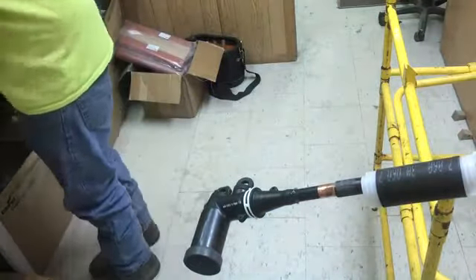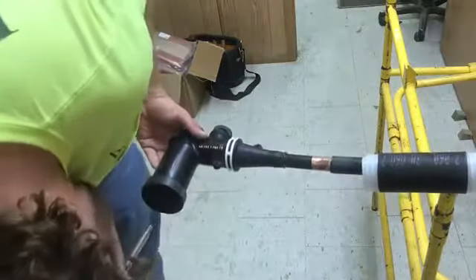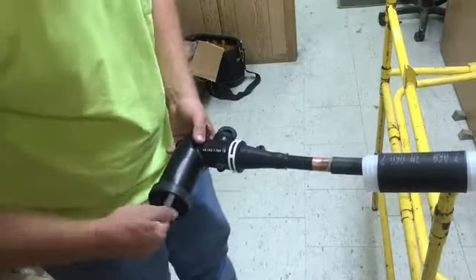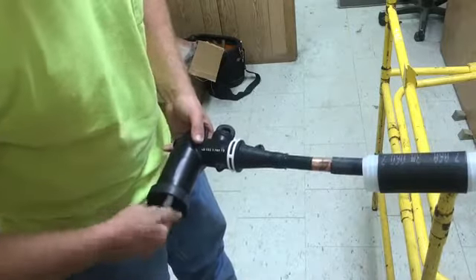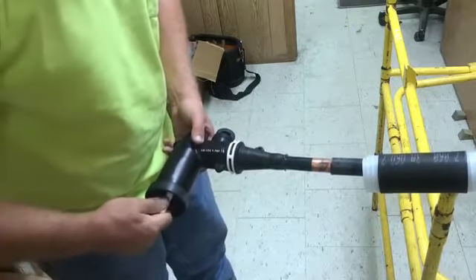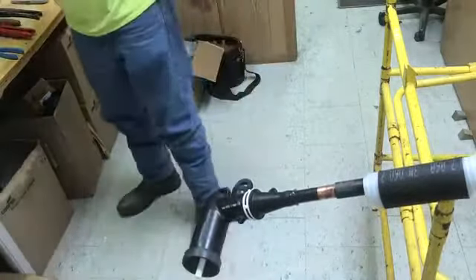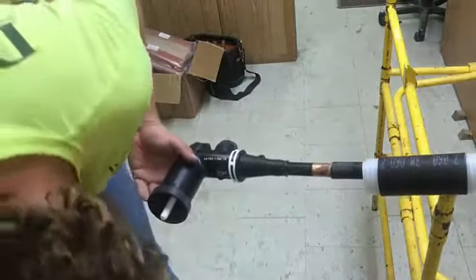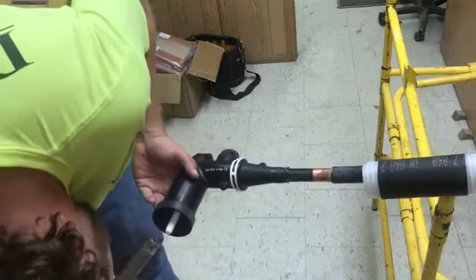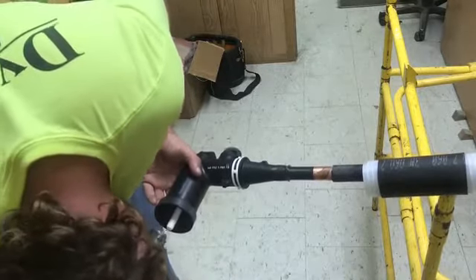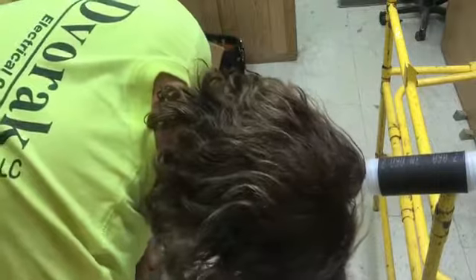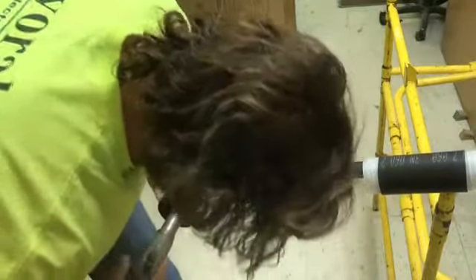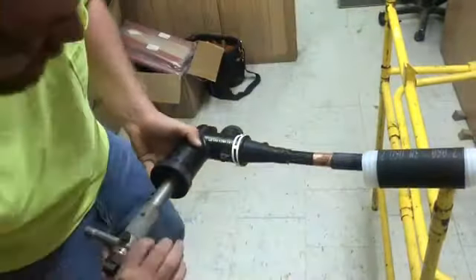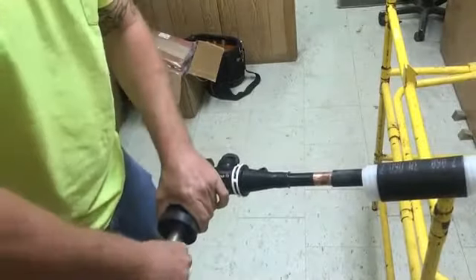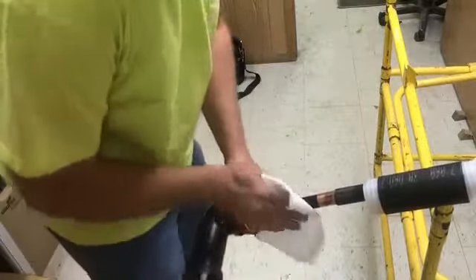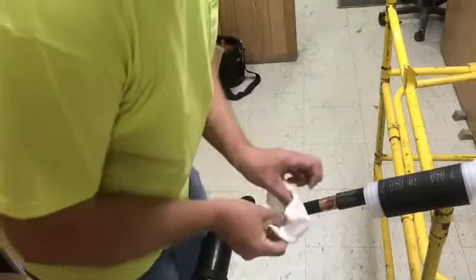Now install the probe. Align the 200 amp elbow with the threaded end of the copper top and install the probe by hand until snug. Make final torque with an appropriate probe insert torque tool or use the factory supplied torque wrench. If using the factory supplied torque wrench, you will turn the torque wrench until the bar is bent. Wipe off any excess silicone grease from the elbow installation.